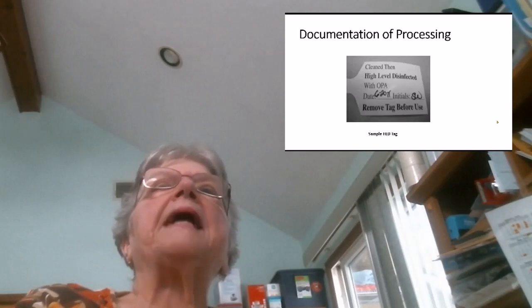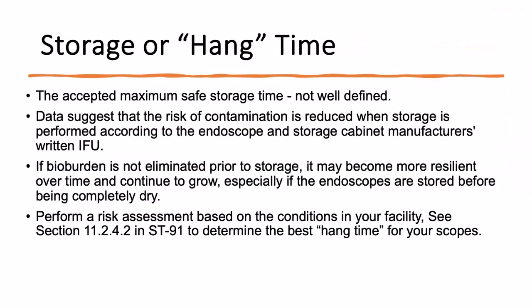The accepted maximum safe storage time really has not been defined. Many organizations have been looking at this. There is some data that says that the risk of contamination is reduced when storage is performed according to the endoscope and storage cabinet manufacturers. If bioburden is not eliminated prior to storage, it may become more resilient over time and continue to grow, especially if the scope is not completely dry. So again, you should do a risk assessment to determine the best hang time for your scopes.